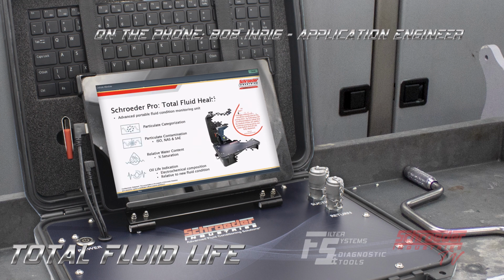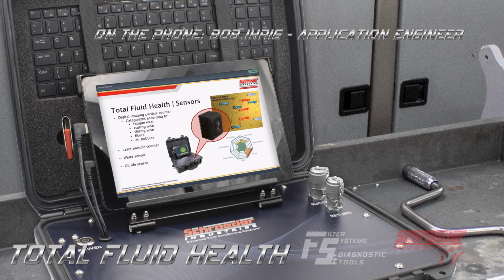So the Schroeder Pro Total Fluid Health is really the big brother to the Total Fluid Life units. It really truly is an advanced, revolutionary, portable fluid condition monitoring unit that not only measures the particulate contamination, relative water content, and temperature, and has the oil life indication capabilities, but it also has the ability to categorize particles into different types of particles. And as you'll see here on the next slide, the digital imaging particle counter categorizes those particles into categories such as fatigue wear, cutting, sliding wear, fibers, and the big one is air bubbles.